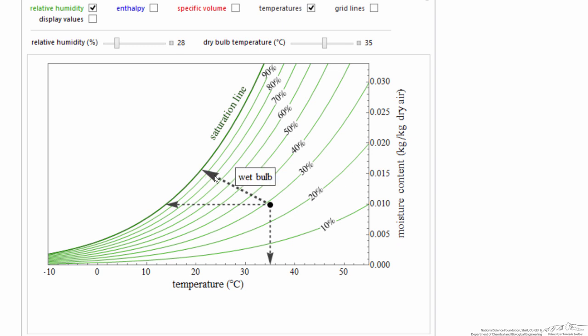Here is the wet bulb temperature. This is the temperature if I were to wrap, for example, cloth around the thermometer, and then move it through the air, I'd get evaporative cooling. Water would evaporate, because we're not at saturation conditions. Water would evaporate, this would cause cooling, because energy for evaporation comes from lowering the temperature, and that temperature I measure would be the wet bulb temperature.